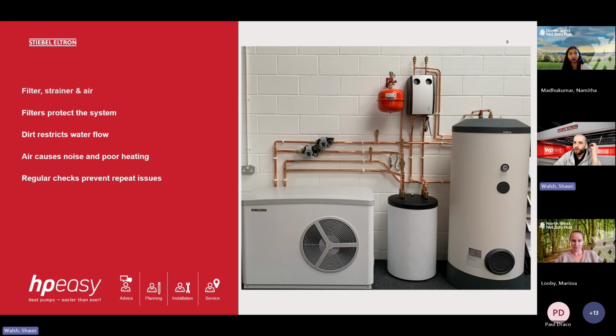So most heat pump problems, they don't start initially as faults. What they are generally caused by is, say, dirt or air or system quality. So, for example, you may have a diverter valve, just as a real world example. The diverter valve's job is to send the heat and water to either the hot water tank or the buffer tank. If over time we have debris building up in the system, this diverter valve can get blocked. If this then blocks, the water is not going where it's intended to, and then the machine can go into fault because it's combating that in the system. Okay.